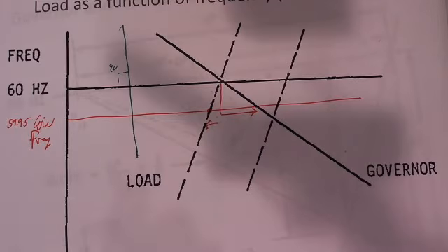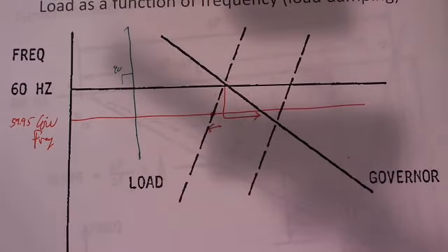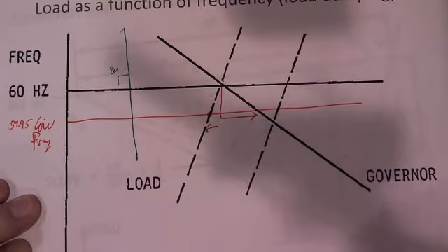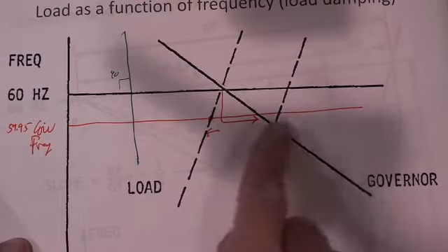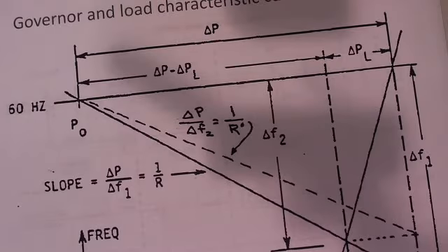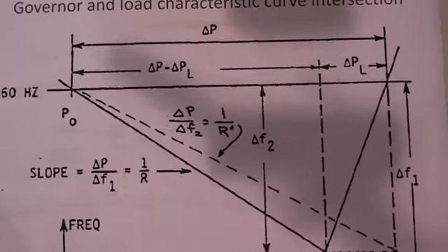Now, you can say, well, wait a minute, that means I'm not generating everything I could from the solar. If it's going to help stabilize frequency and participate in frequency control, then it has to accept the fact that the solar cell does not produce maximum all the time. But that's the disadvantage. But you can do that. You can bend this green characteristic so that it looks like this one. It can go from this to this by internal feedback inside the inverter.